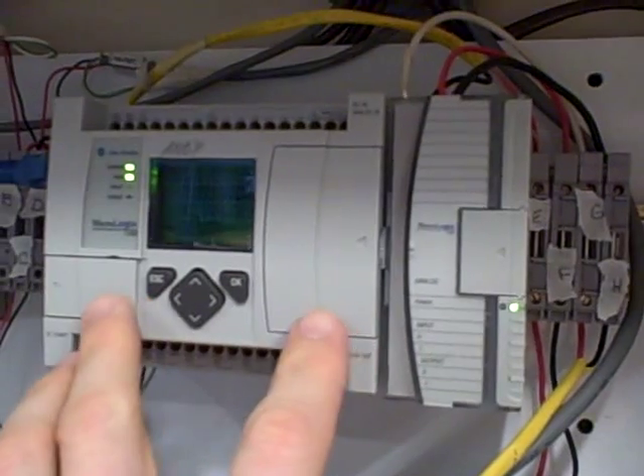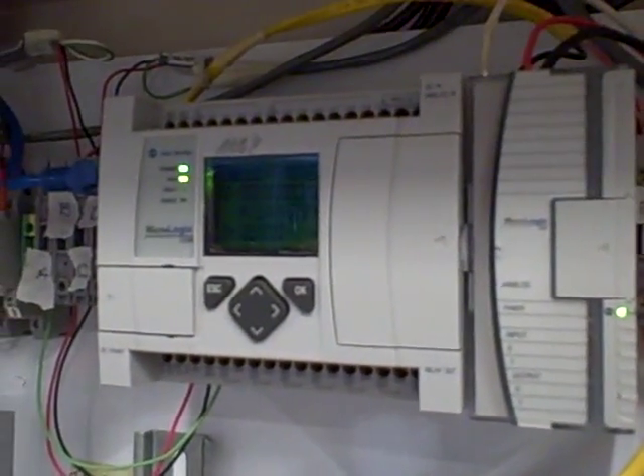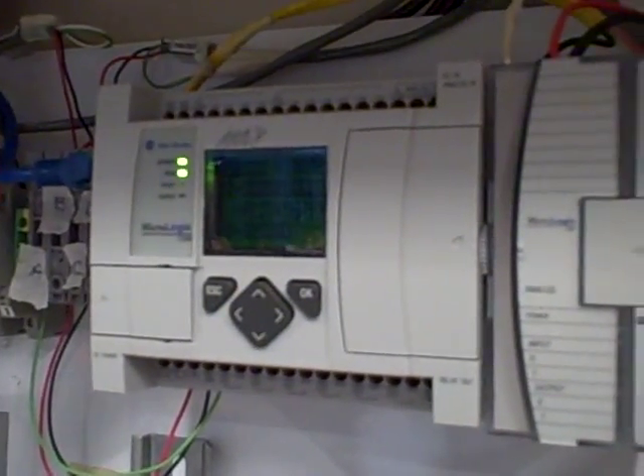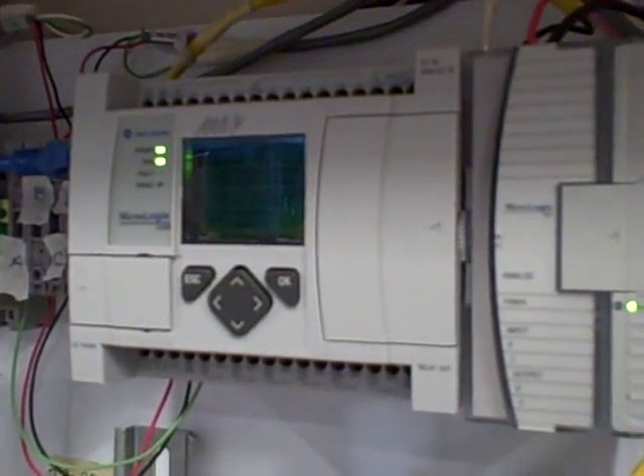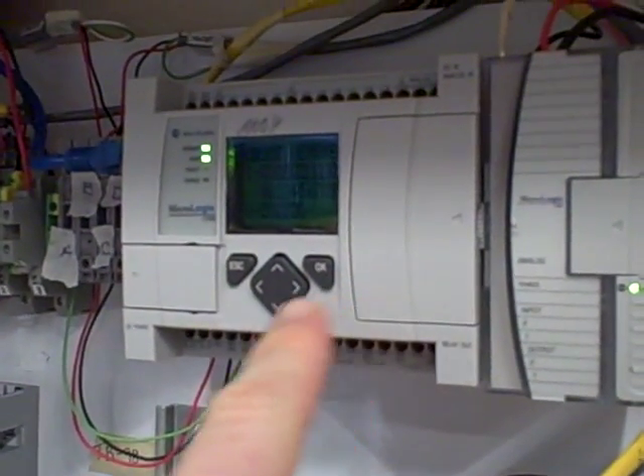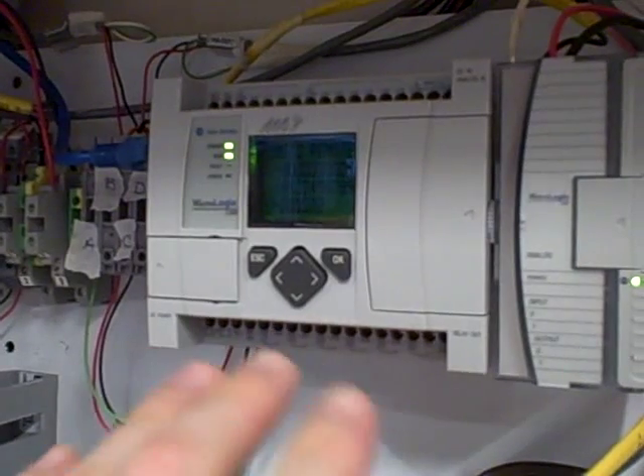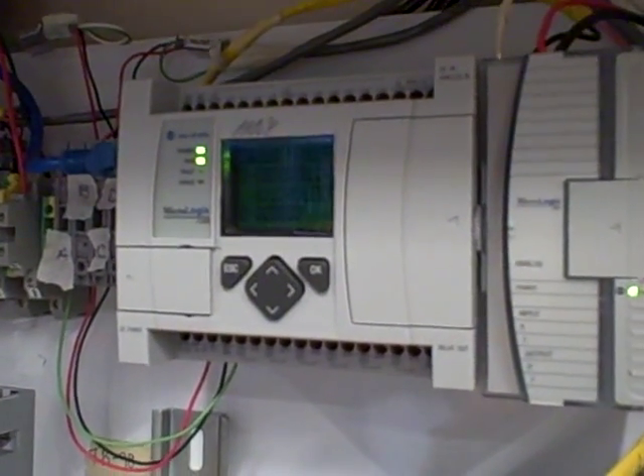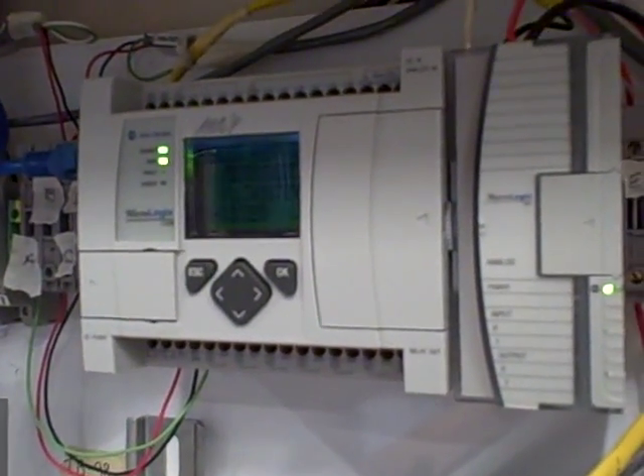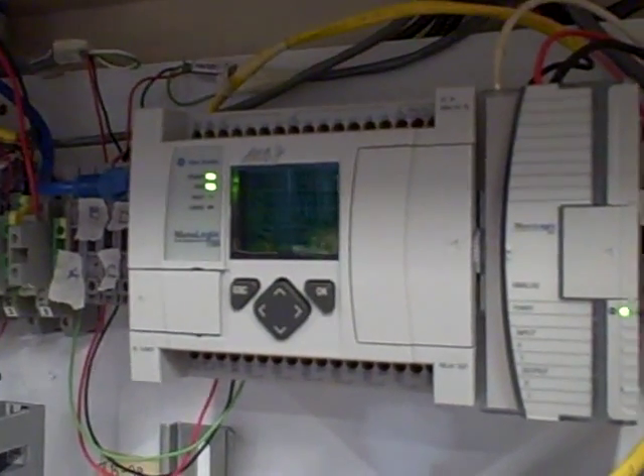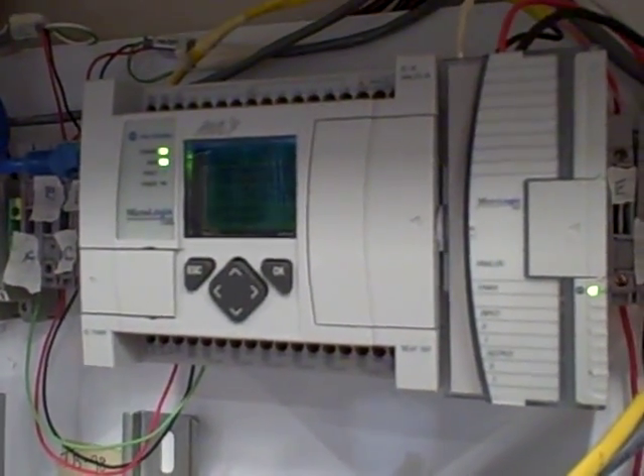The MicroLogix PLC implements a PID control instruction to do the proportional integral derivative control. So we can enter a set point value into this. We can have auto manual mode, direct reverse acting, and various degrees or values of P, I, and D to tell it how aggressive to be in its control.